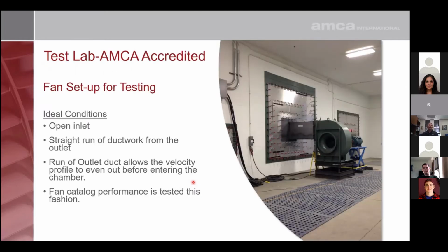Now, here we have a fan in an AMCA accredited test lab. And I'm not sure if everybody's familiar with AMCA. AMCA is the Air Movement and Control Association. And it's basically the organization that gives all fan manufacturers that conform to AMCA a methodology for doing 3 things. That is testing the fan for airflow and pressure, testing the fan for sound, and finally, testing the fan for vibration. They give us the procedures on how to test the fan.